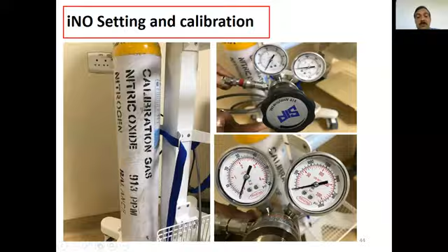This is the regulator. As I mentioned, this regulator is also expensive. It costs about 1 lakh rupees, but is a one-time investment. And here there are two dial systems. The first dial is the nitric oxide cylinder pressure, and this should be 200 psi. The second is the nitric oxide delivery output, and this should be at least a minimum of 1 bar. So both should be working, and when you connect it, you should check both before we connect to the nitric oxide.